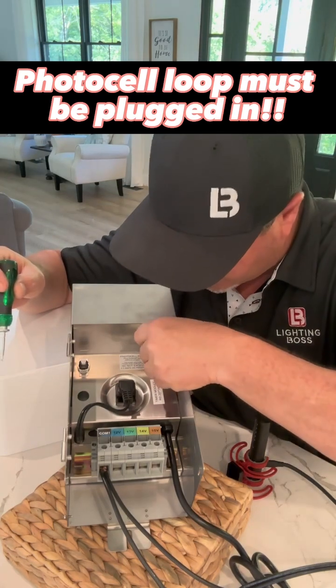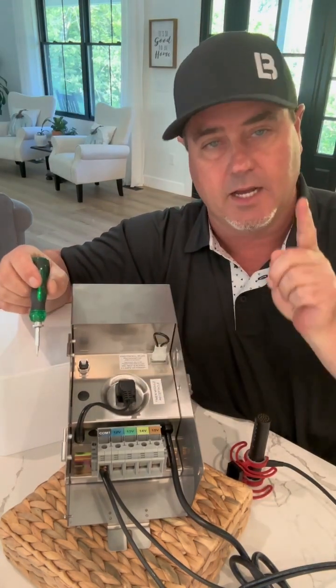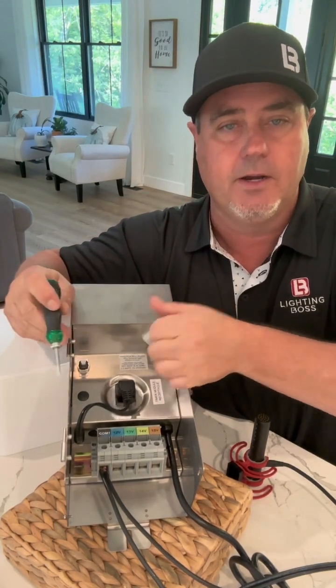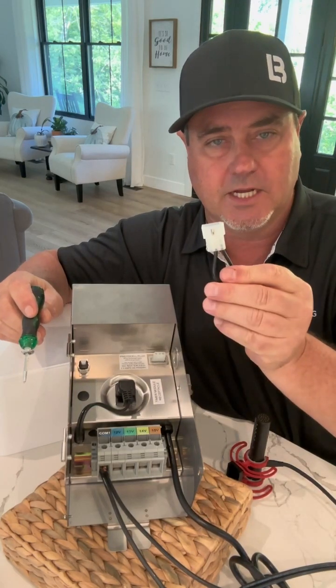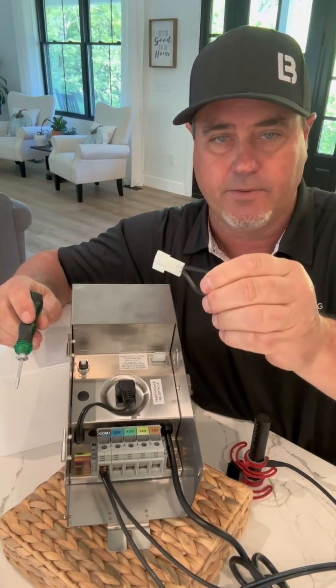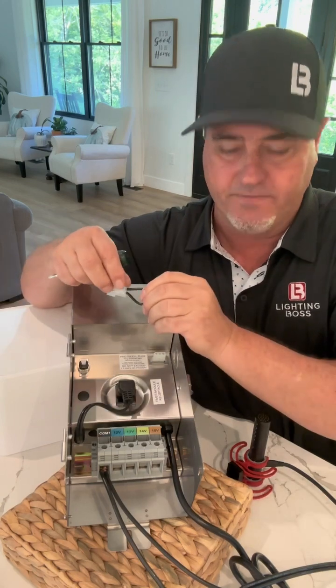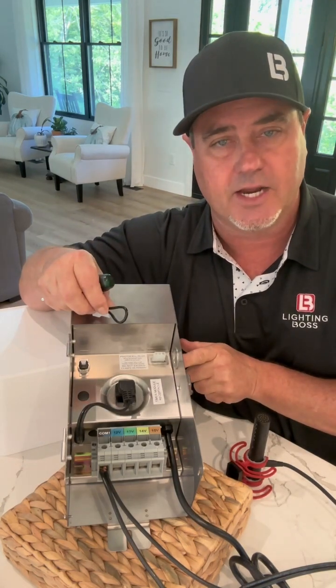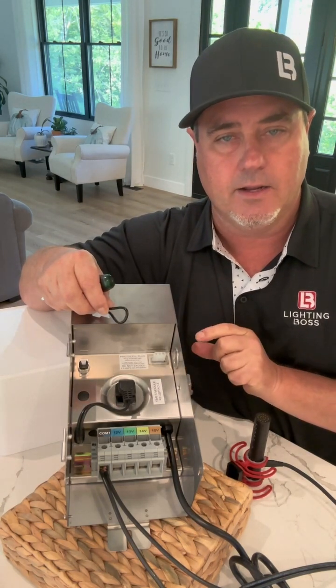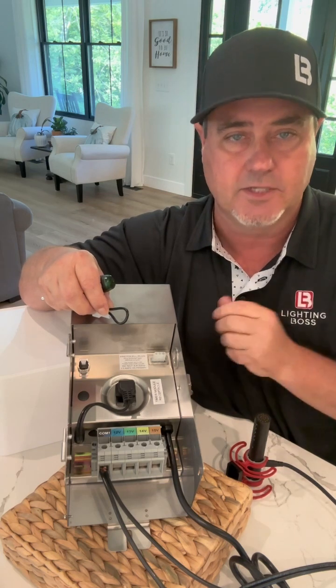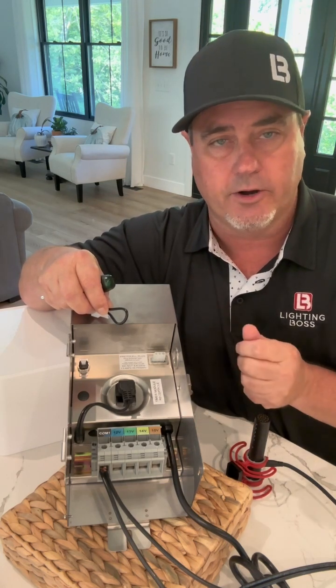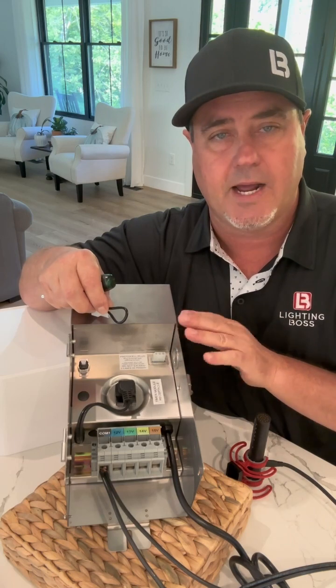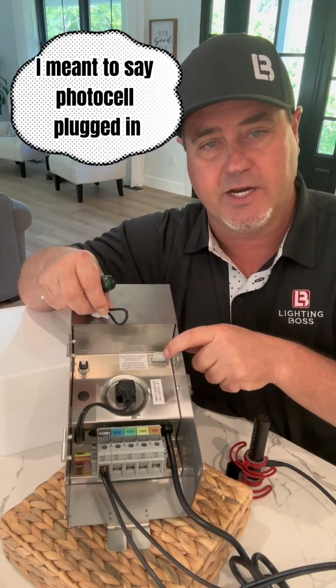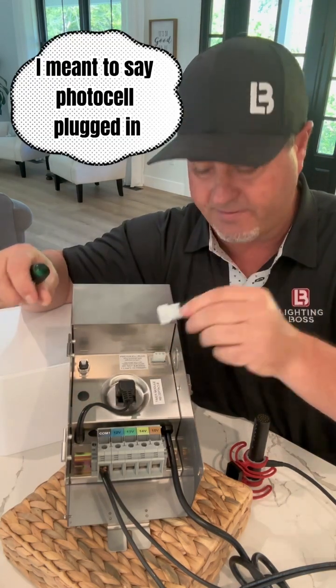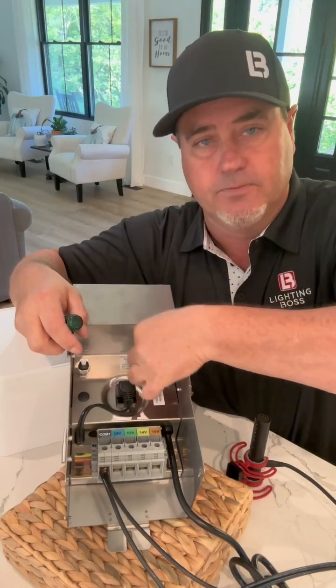So this has to be plugged in at all times unless you're going to be running a photocell that will have an attachment that looks very much like this one, and the photocell can mount on the side of the actual box, and it'll read dusk to dawn and turn your transformer on and off. So for your transformer to operate, you'll either need to have that photocell plugged in, or you're going to need to have this loop plugged in as well.